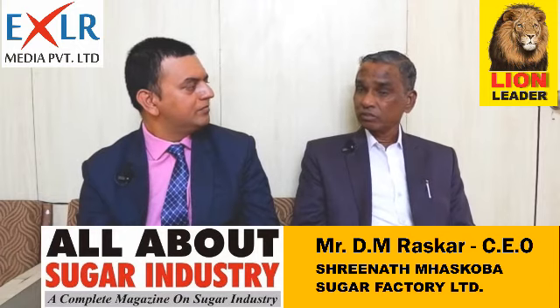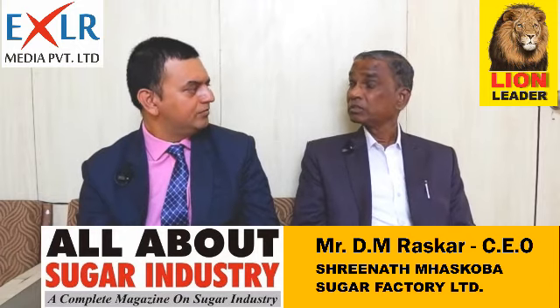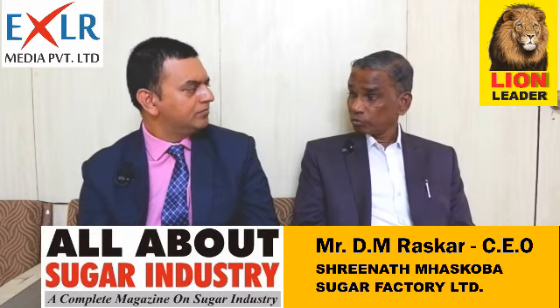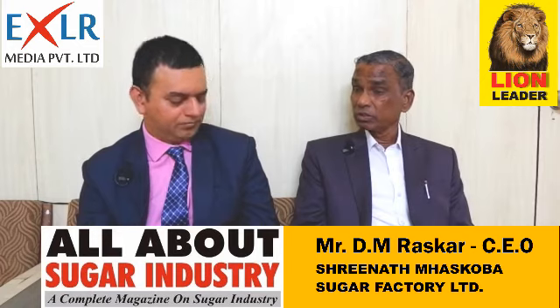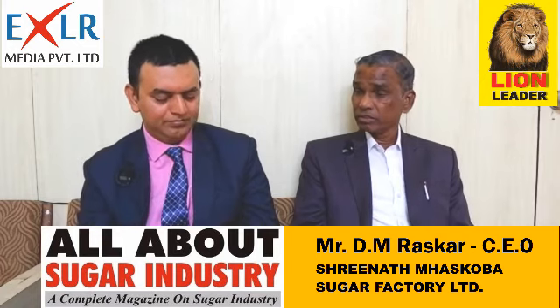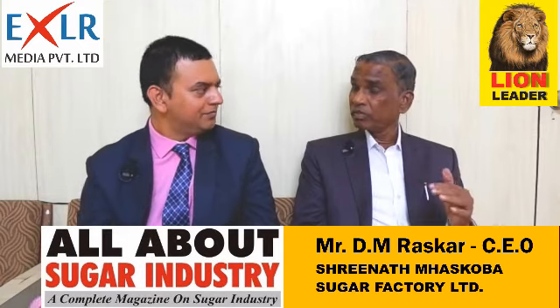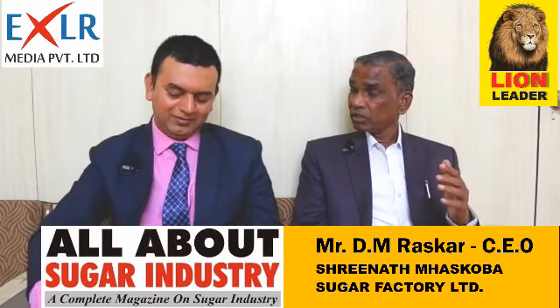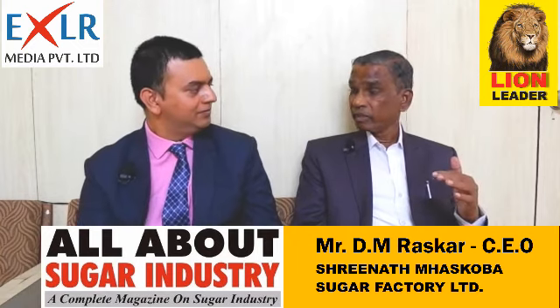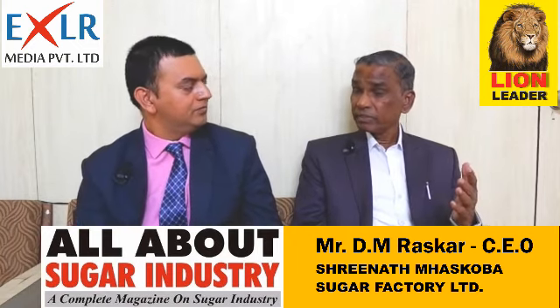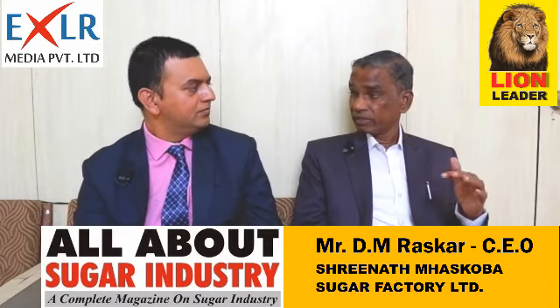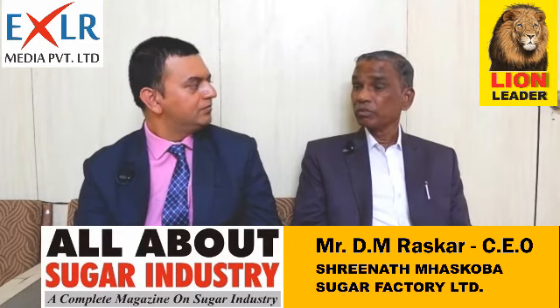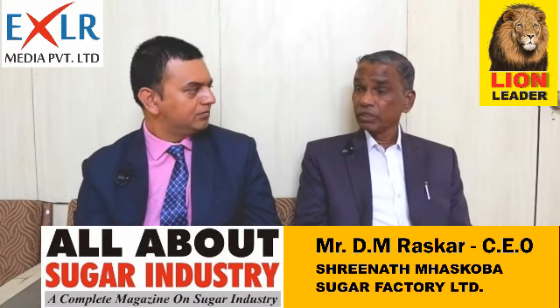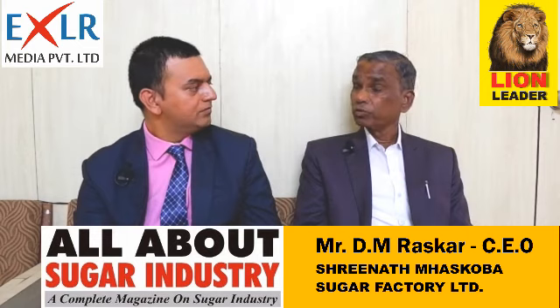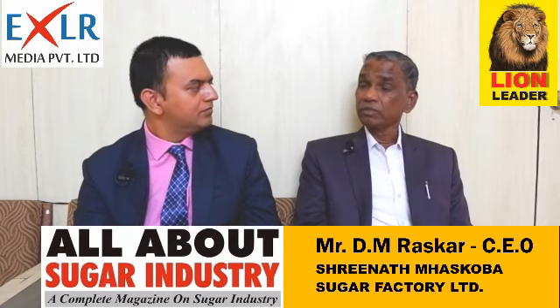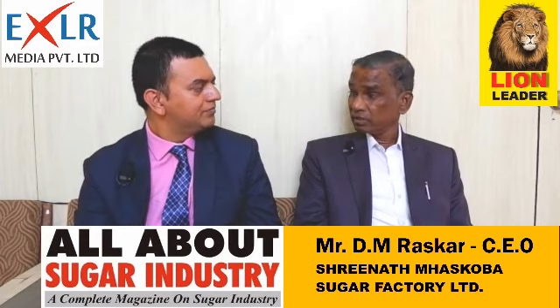But our boilers were not suitable to burn this type of fuel. We have two boilers, one of 32 tons per hour capacity and another of 70 TPH. So we decided to modify that 32 TPH boiler with a traveling grate, made the investment, and modified the furnace. Now we are using this RDF from the corporation, about 15 to 20%, along with bagasse, and it is burning very nicely.